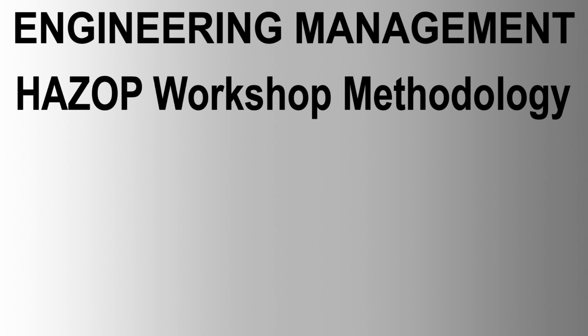1. Preparation. Define scope. Clearly define the scope and objectives of the HAZOP study, including the boundaries of the system or process to be examined. Assemble team. Gather a multidisciplinary team with expertise in process design, operations, safety, and maintenance. The team typically includes a HAZOP chairman, a scribe, process engineers, control engineers, operations personnel, and safety specialists.